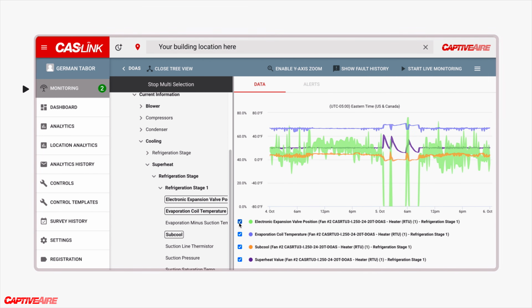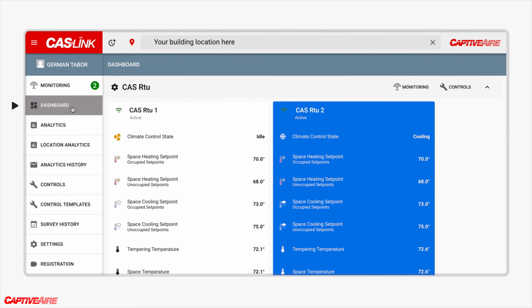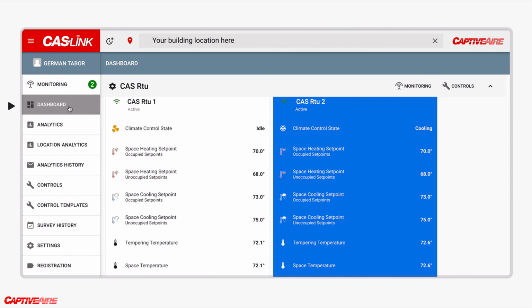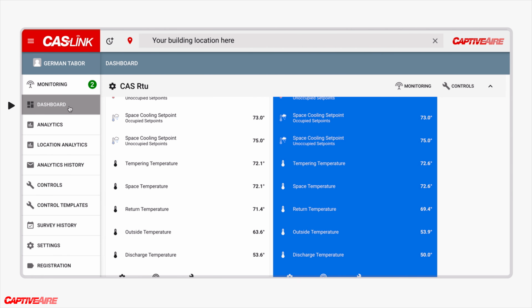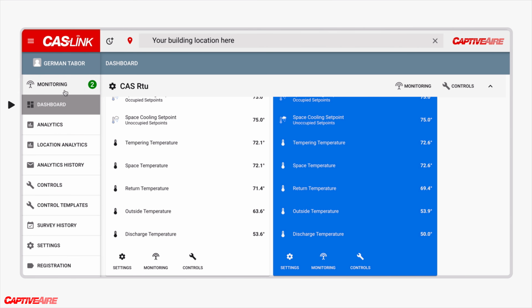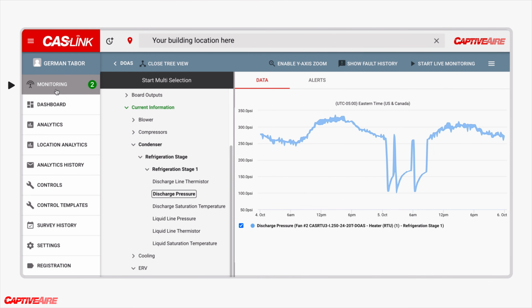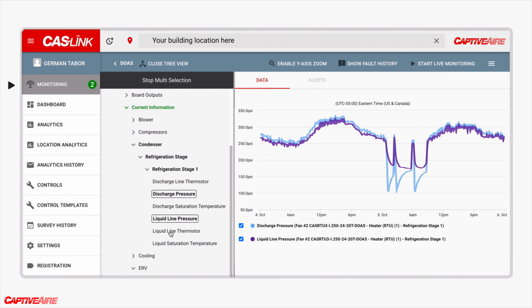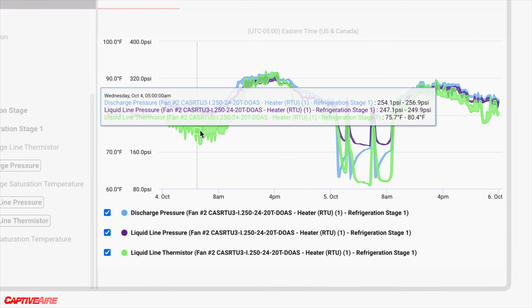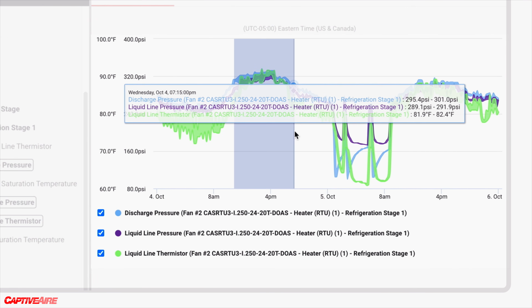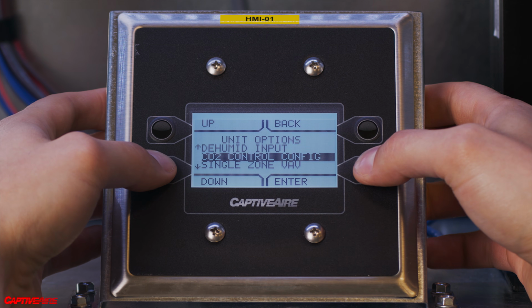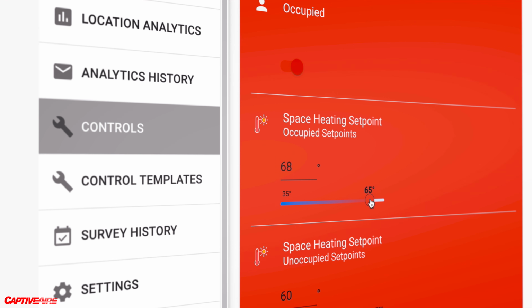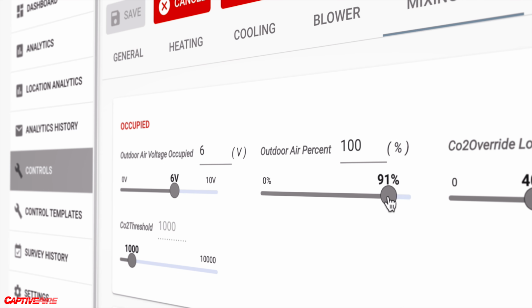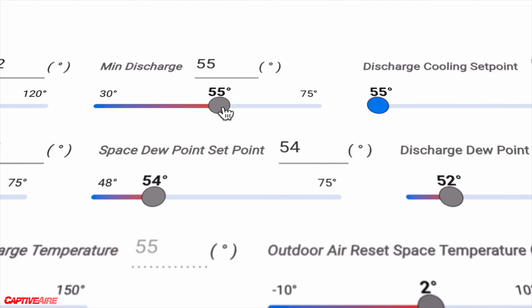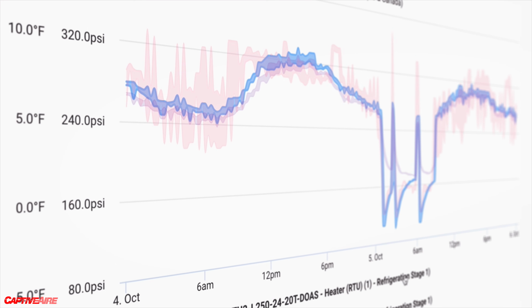And when you've got this much data, it can be overwhelming for an end user. So we also have a dashboard, which provides a quick snapshot of each unit, as well as its basic set points. That way, we're able to provide a simplified view for users, while an engineer can access more specific, granular data. This data can be visualized individually or combined in order to better understand the interactions happening within the unit. And finally, anything that could be controlled by a technician at the unit's interface can also be controlled within CASLink. From simple set point tweaks to more complex parameters, an engineer can make remote changes and see how the system is affected in real time.